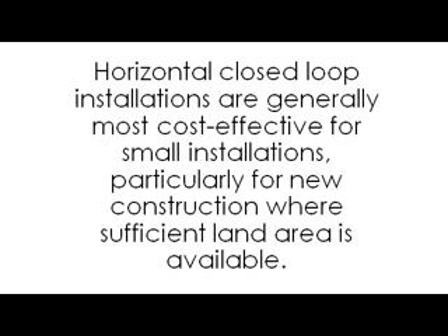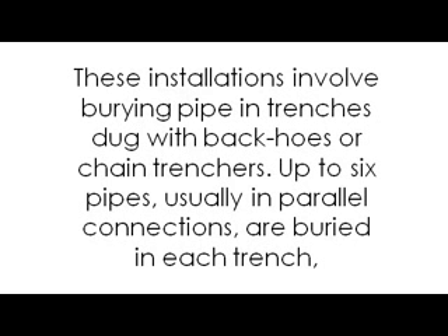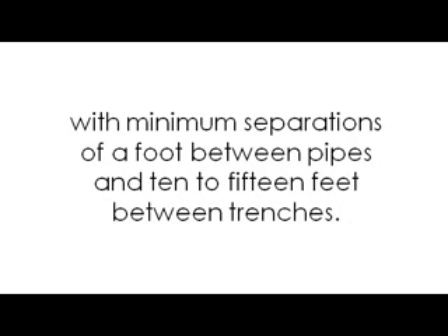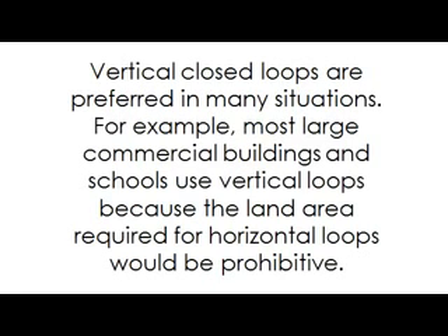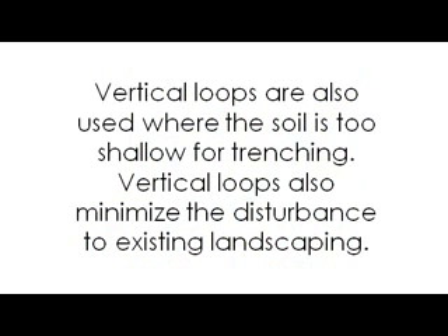Horizontal loops. Horizontal closed-loop installations are generally most cost-effective for small installations, particularly for new construction where sufficient land area is available. These installations involve burying pipe in trenches dug with backhoes or chain trenchers. Up to 6 pipes, usually in parallel connections, are buried in each trench, with minimum separations of a foot between pipes and 10 to 15 feet between trenches. Vertical loops. Vertical closed loops are preferred in many situations. For example, most large commercial buildings and schools use vertical loops because the land area required for horizontal loops would be prohibitive. Vertical loops are also used where the soil is too shallow for trenching.